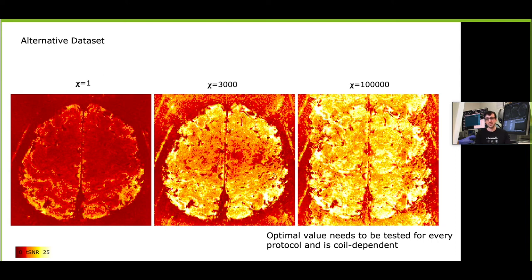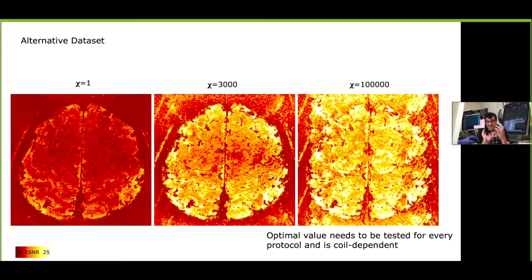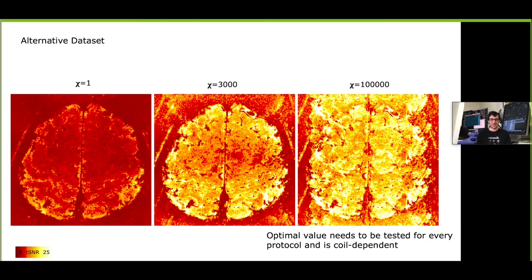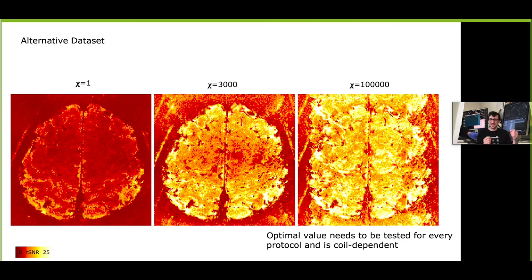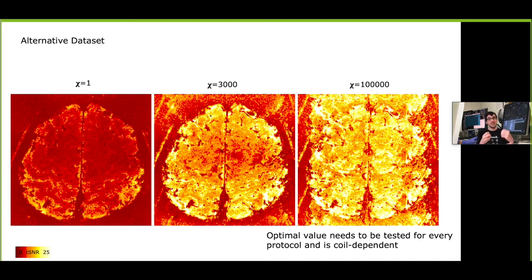Usually however I think that the default is way too conservative. We can be much more liberal and end up with much better tSNR values. You can basically choose the tSNR that you want to have. I find it kind of funny how in the history of MRI or fMRI there was so much focus on sequences. There's no question that when you do knee imaging at 1.5 Tesla with a single channel or maybe four channel coil you use a different sequence as if you do very high resolution functional fMRI across layers in the cortex with very small RF channels. However, on the reconstruction side we're still using the same GRAPPA. Why should we optimize the sequence and not the reconstruction? I think there's a lot of leeway and way for improvement for layer dependent fMRI by changing the reconstruction such as here the regularization strength.